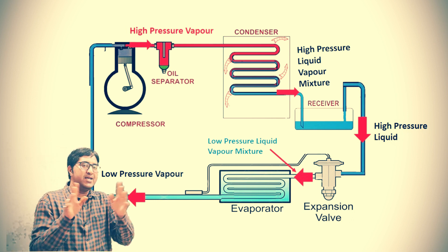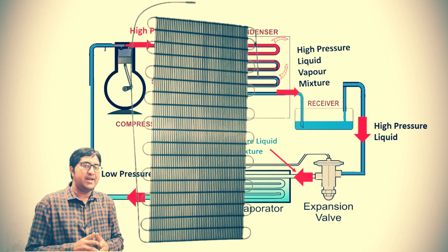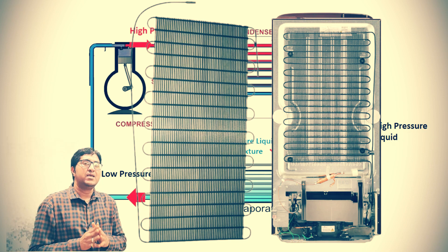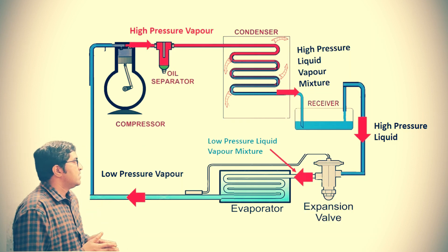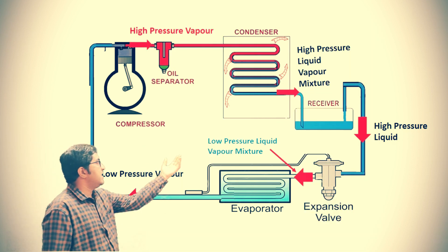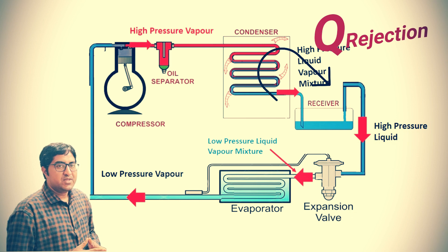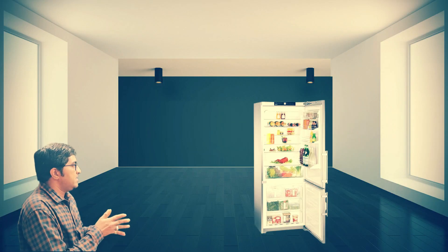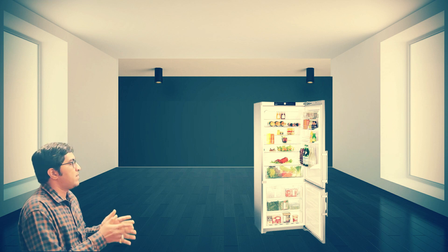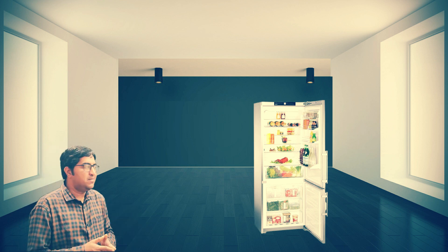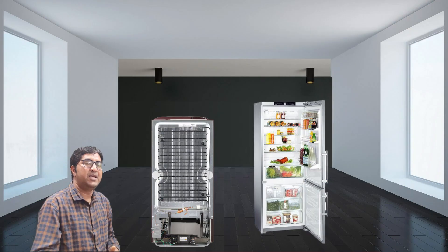The condenser is a type of heat exchanger and it is mounted on the outside of the refrigerator. You can see that a large coil is mounted outside — that is the condenser. The function of the condenser is to reject heat to the surrounding. We maintain a sufficient gap of 2.5 to 5 inches so there is proper circulation of heat, since the condenser rejects heat to the surrounding.